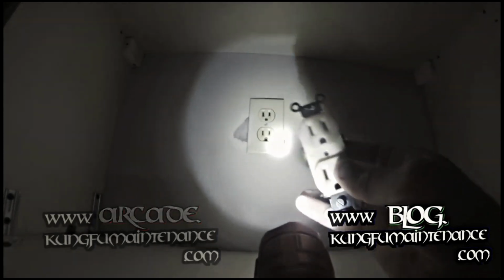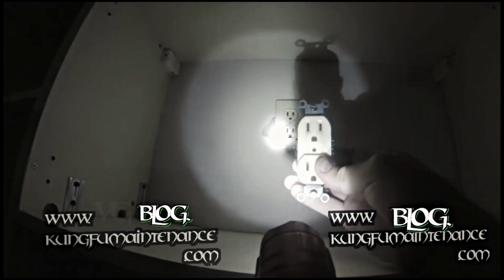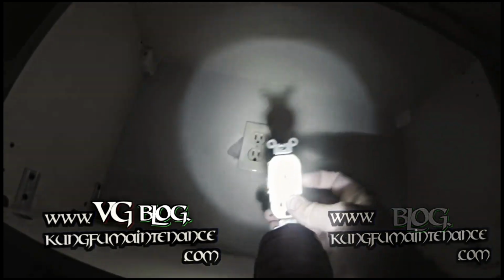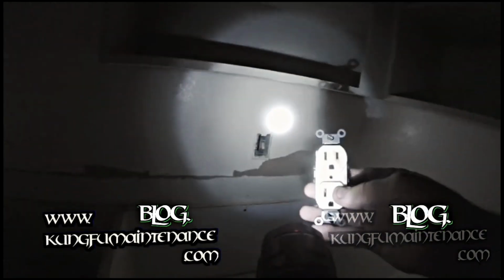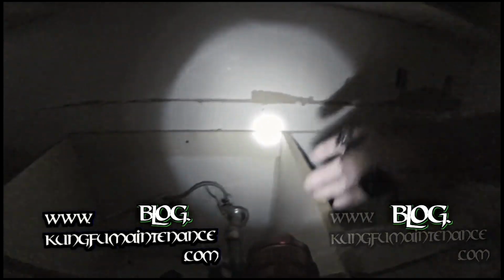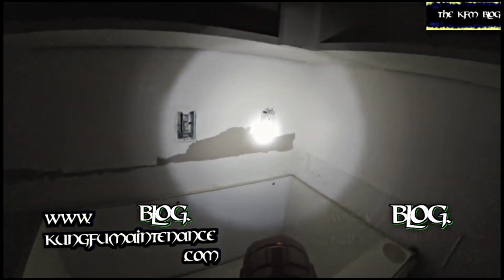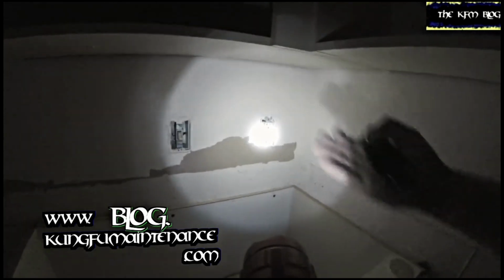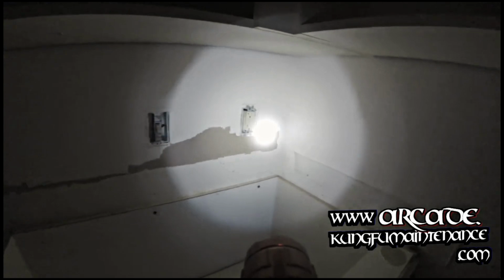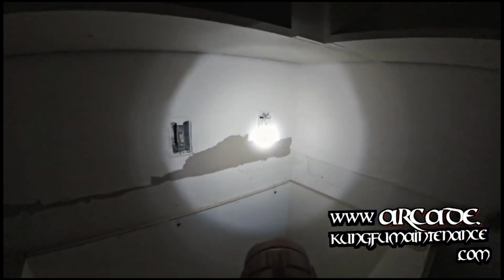Here was the outlet, and if you look right there, the breakaway tab for this particular situation is not broken. Normally when you see a breakaway tab, it's for a switched outlet somewhere down the line, although it's possible for it to be broken for its own circuit in some applications. You often see that for the outlet where the garbage disposal and dishwasher are plugged in. They're each on a dedicated circuit, so they each have their own hot wire coming in. Often just the hot side breakaway tab is broken, and the neutrals are shared because they all meet up at the breaker panel.